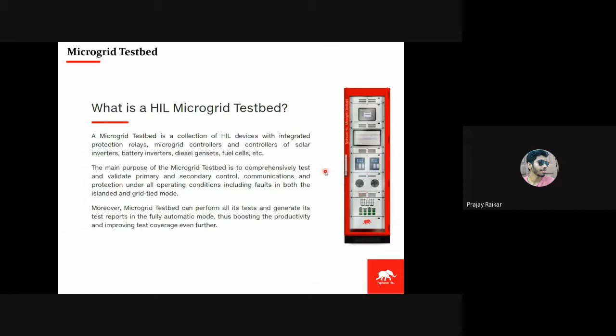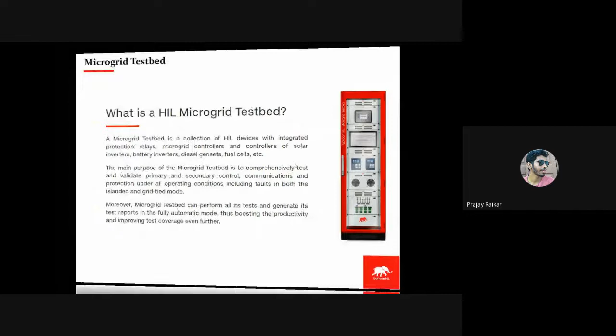Coming to the microgrid testbed, this generally has a collection of many HIL devices along with microgrid controllers. There are different interfaces and controllers that can be integrated depending on customer requirements, such as a protection relay, distributed energy controllers like a genset controller, energy storage system controllers, such as a battery energy storage controller since we're focusing on batteries today, and also a PV controller.